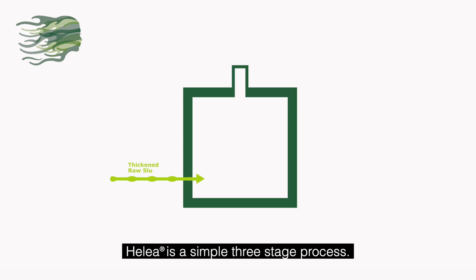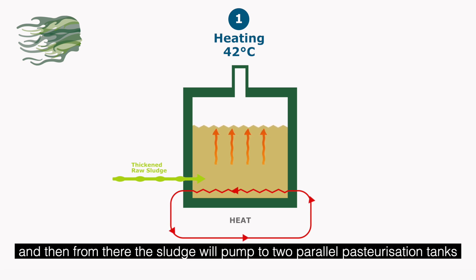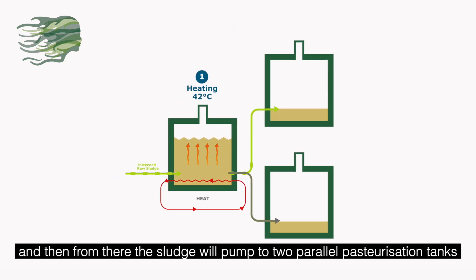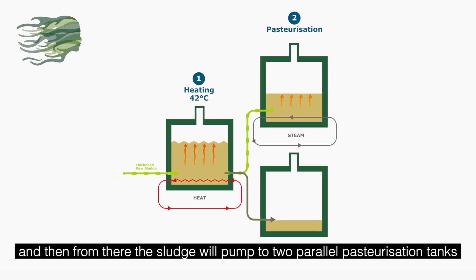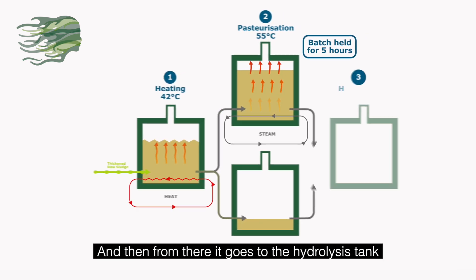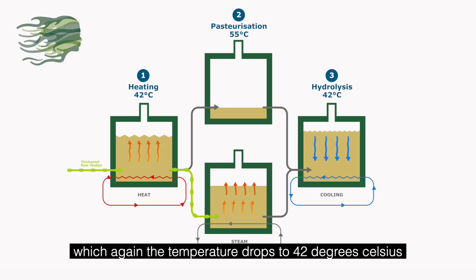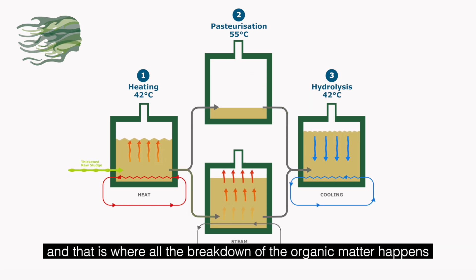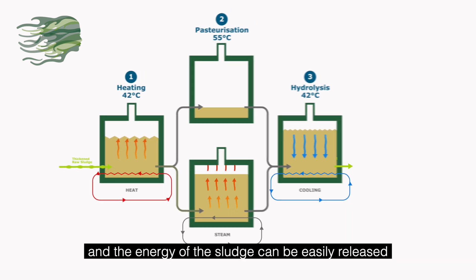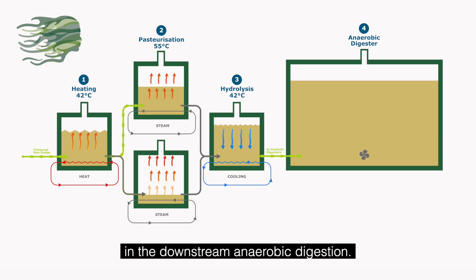Helea is a simple three-stage process. The first stage is a heating stage where you heat up the sludge to 42 degrees Celsius. From there the sludge is pumped to two parallel pasteurisation tanks at 55 degrees Celsius. It then goes to the hydrolysis tank, where the temperature drops back to 42 degrees Celsius and that is where all the breakdown of organic matter happens, allowing the energy of the sludge to be easily released in the downstream anaerobic digestion.